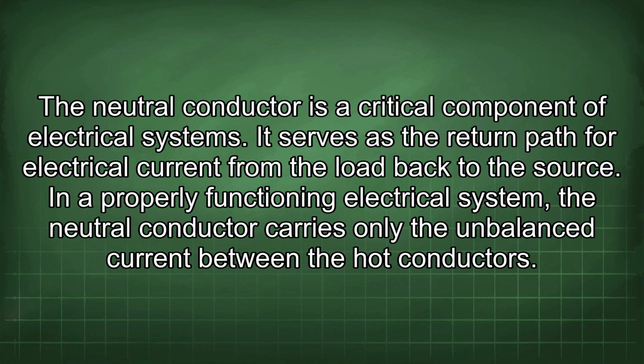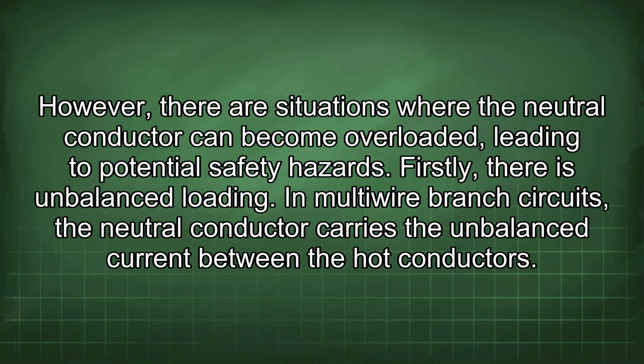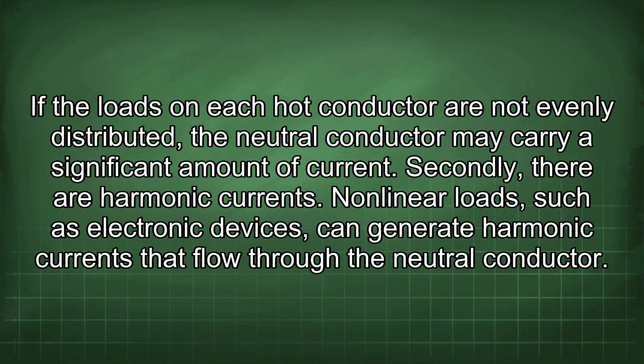In a properly functioning electrical system, the neutral conductor carries only the unbalanced current between the hot conductors. However, there are situations where the neutral conductor can become overloaded, leading to potential safety hazards. Firstly, there is unbalanced loading. In multi-wire branch circuits, the neutral conductor carries the unbalanced current between the hot conductors. If the loads on each hot conductor are not evenly distributed, the neutral conductor may carry a significant amount of current.